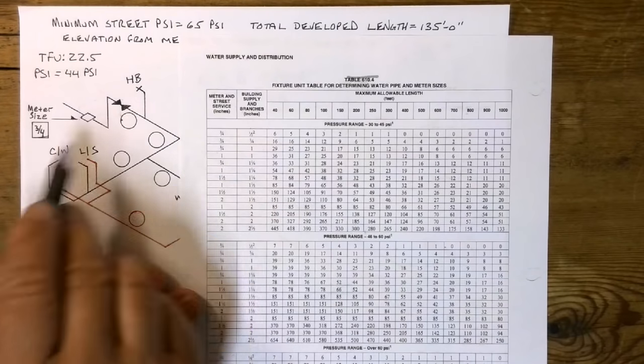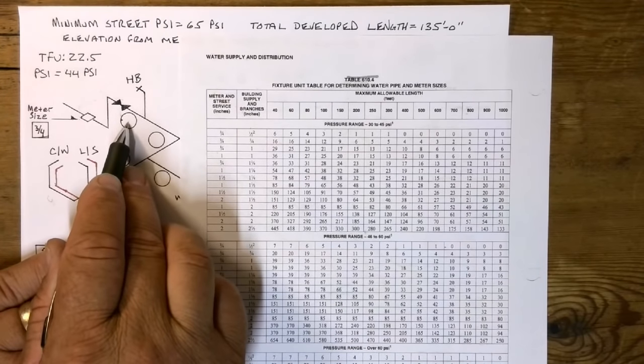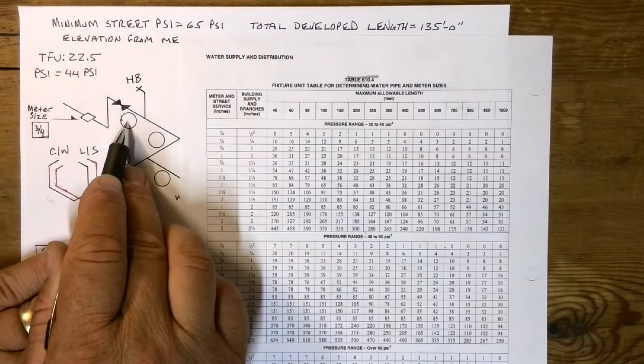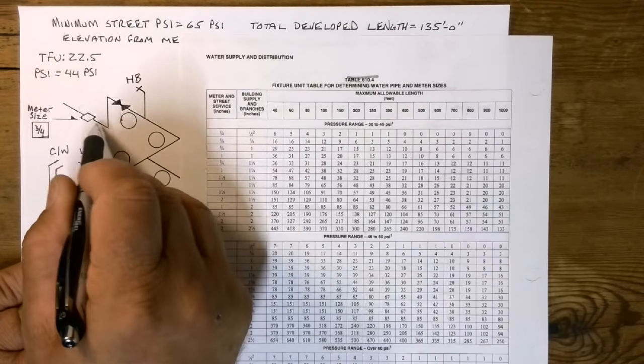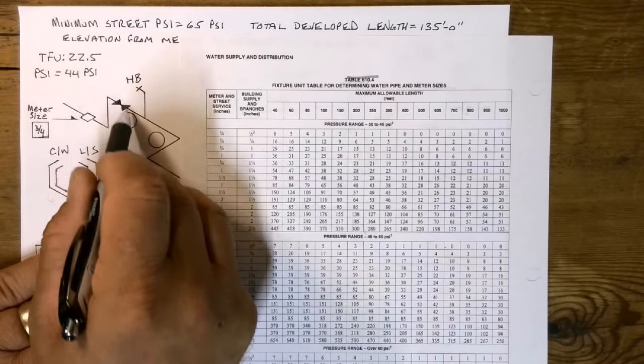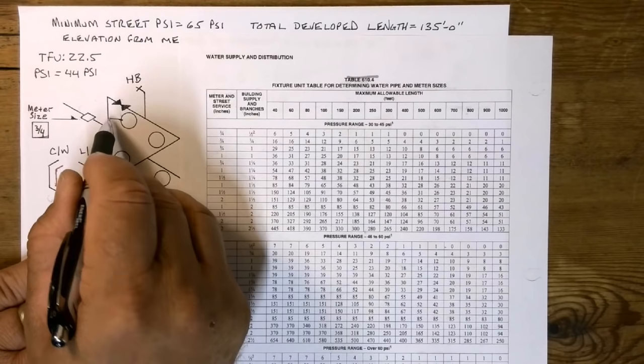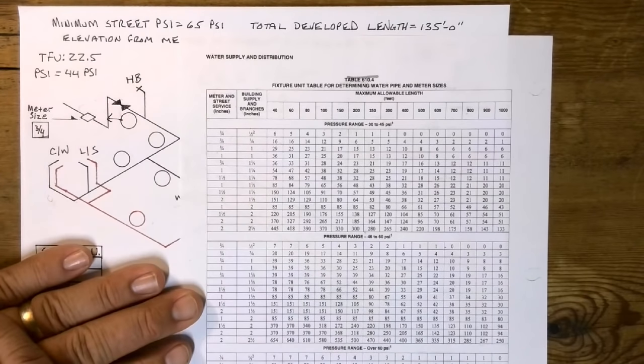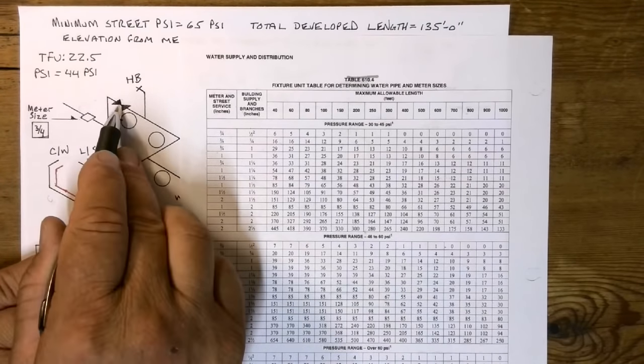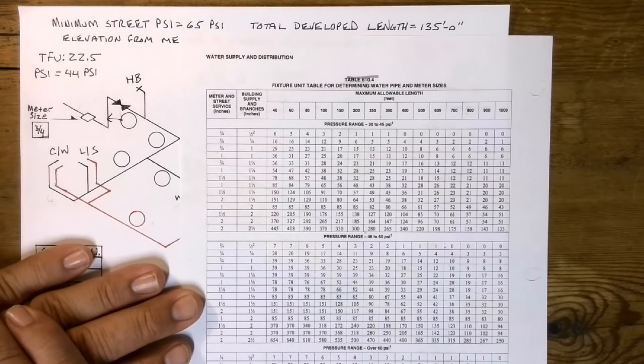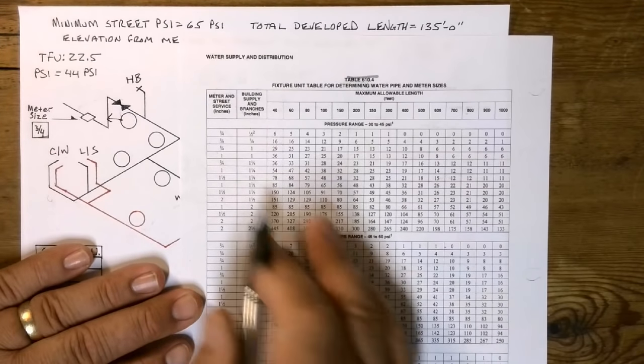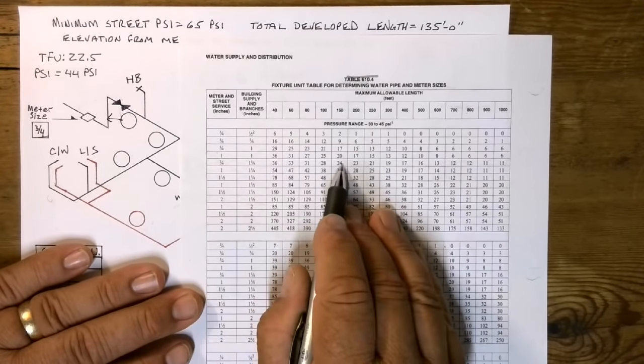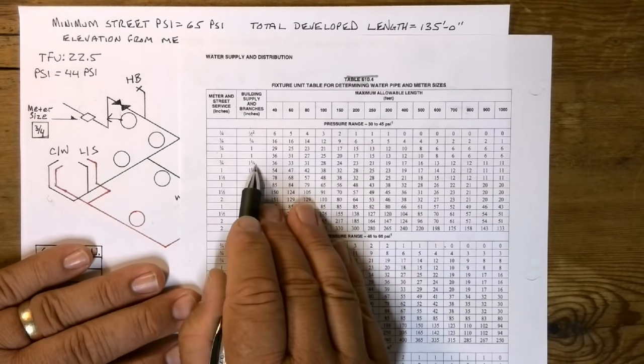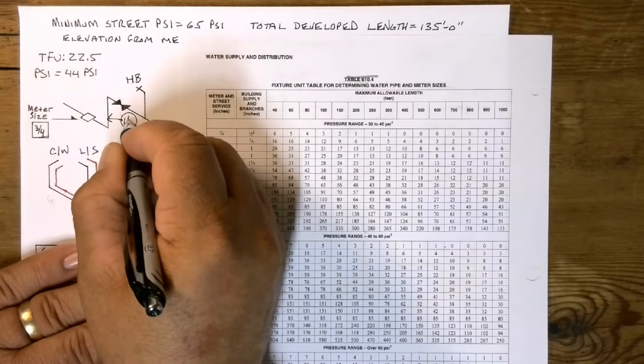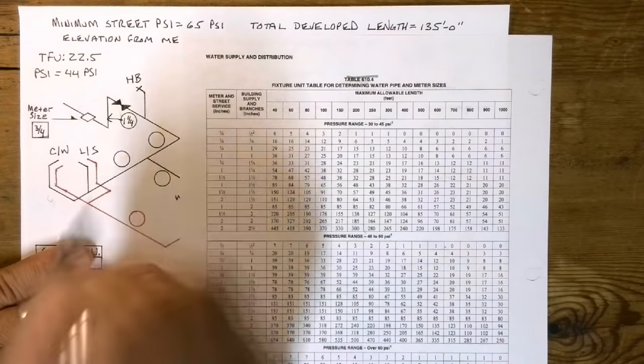And then I got building supply, which is right here, or here, depending on how you want to look at it. This whole run of pipe. Technically, that's your building supply. Before the shutoff valve is going to be your building supply. My building supply, based on 24 fixture units, is 1¼. So we're going to go ahead and make this 1¼, okay?